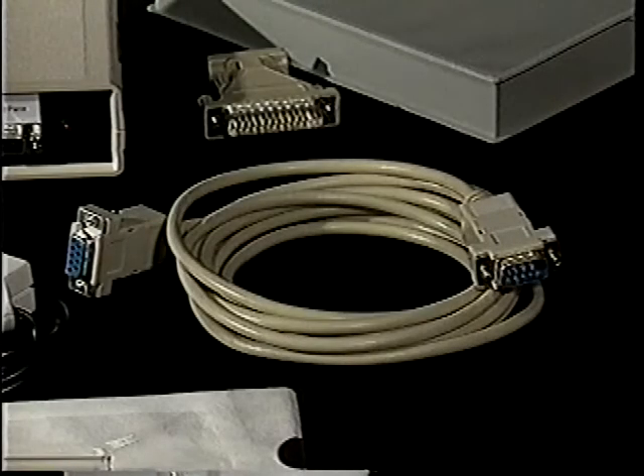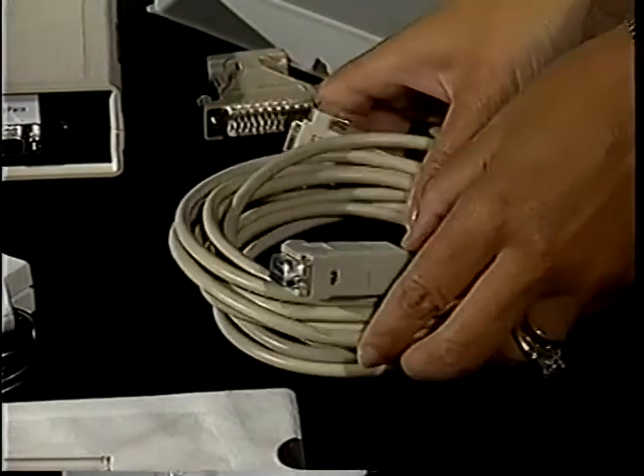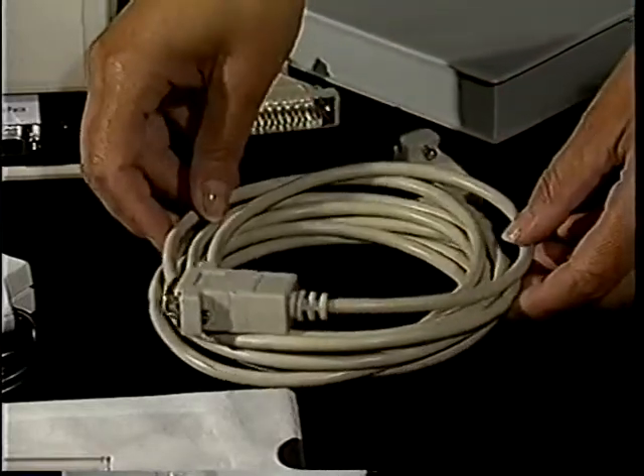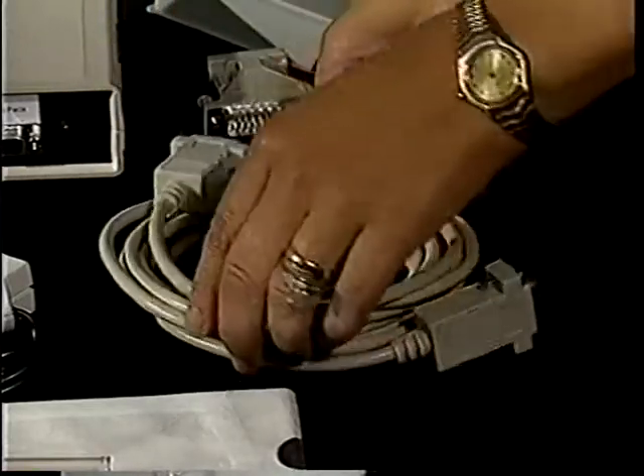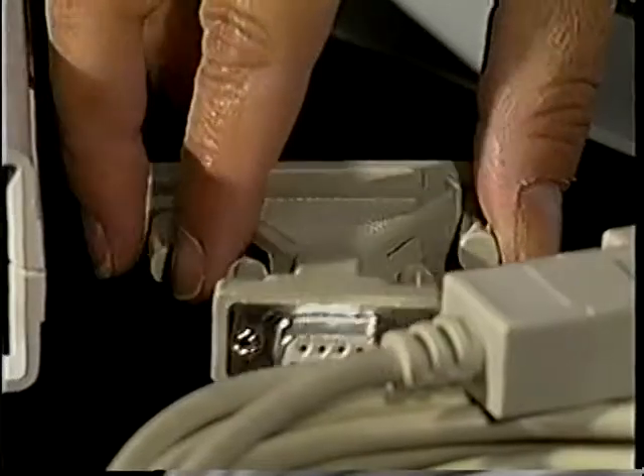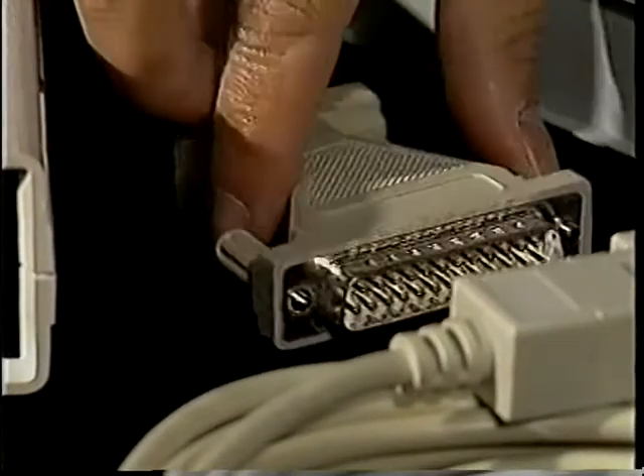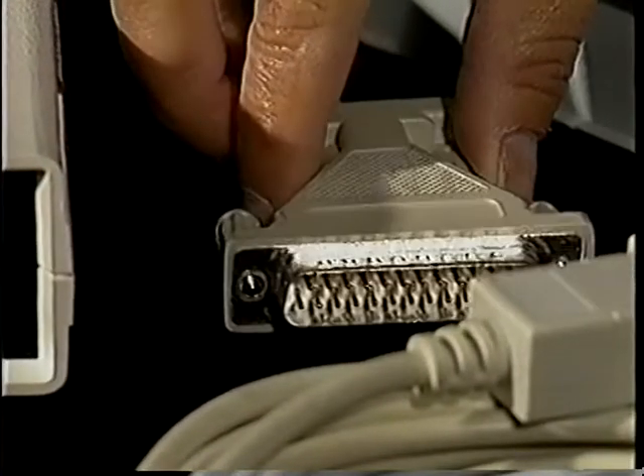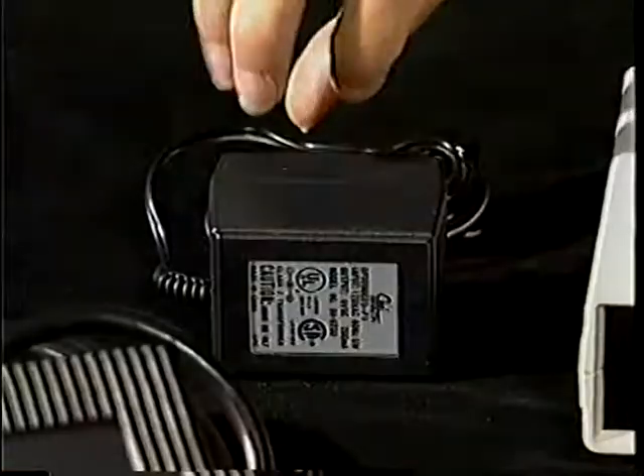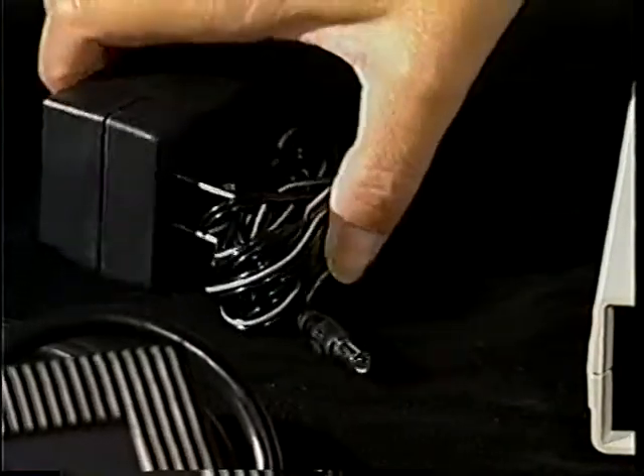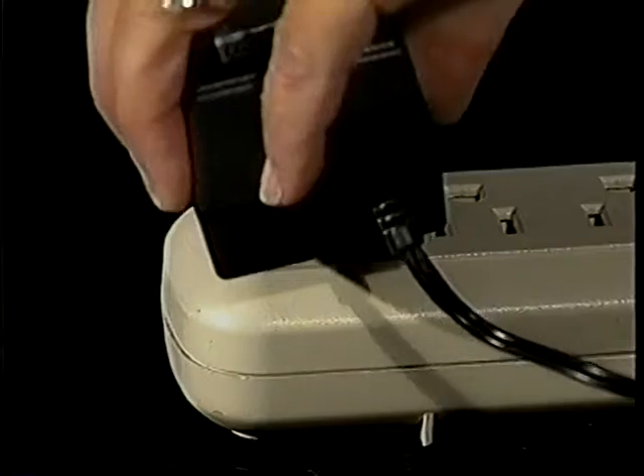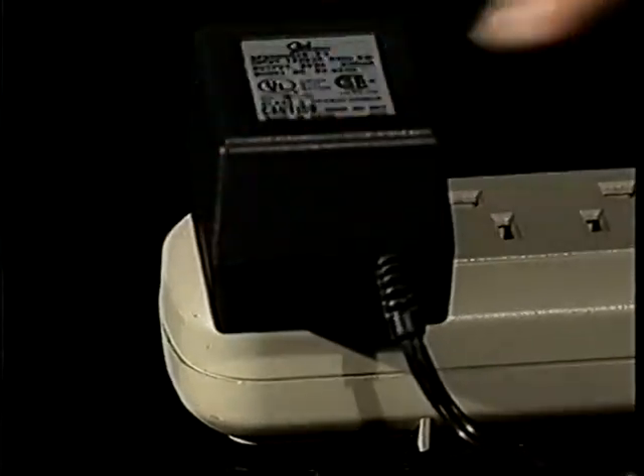The serial cable is a standard 9-pin serial cable which allows the interface unit to send the measured pocket depths to your computer charting program. If you need to extend the cable, an extension can be purchased at your local computer store. Some older computers may require a 9 to 25-pin serial adapter, which can be purchased from a computer store as well. The power supply allows the Probe One to be plugged into any standard 120-volt wall outlet.